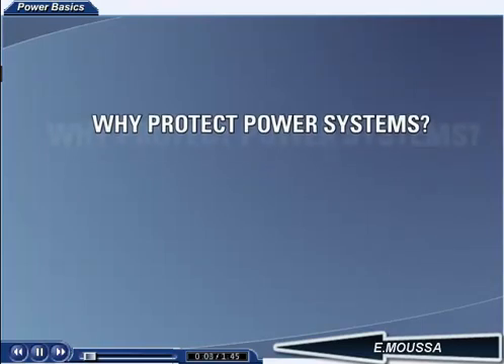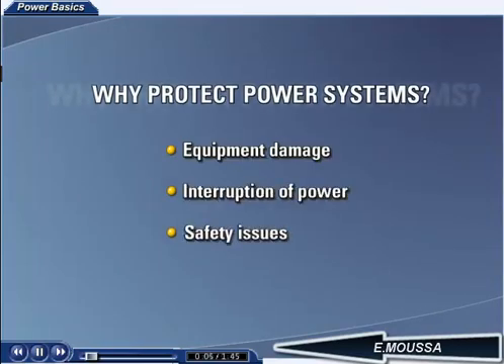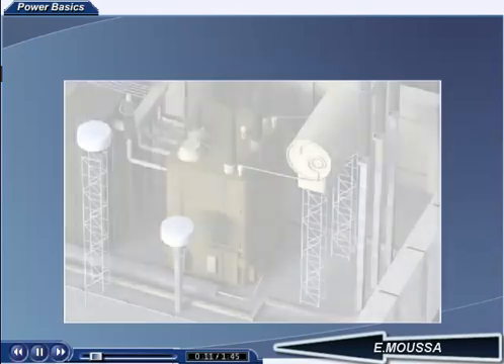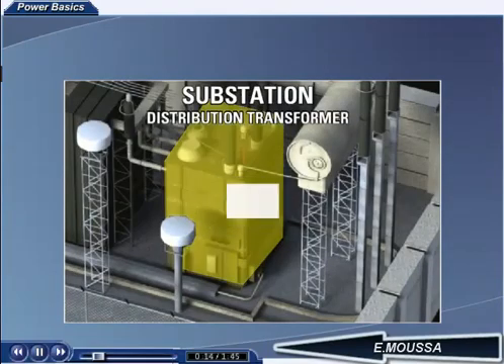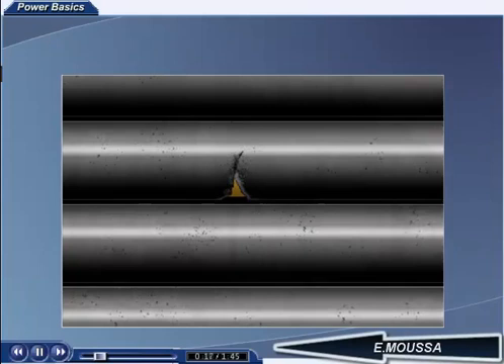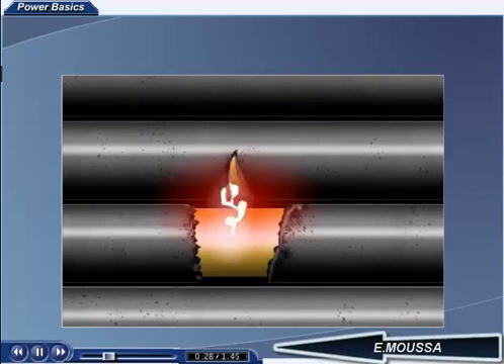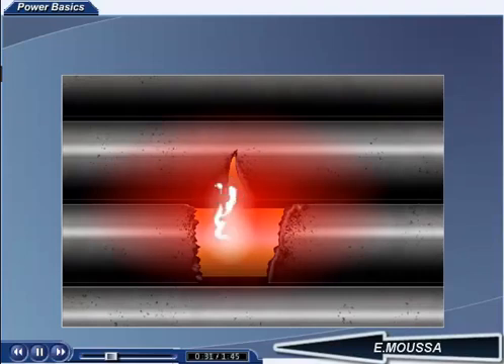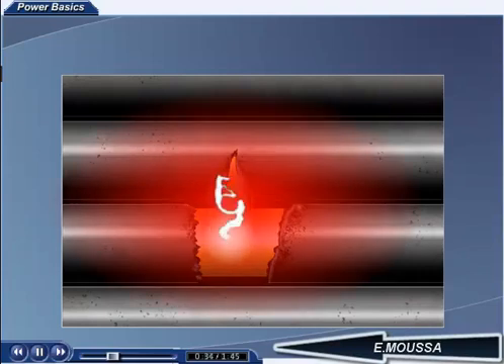The potential costs due to equipment damage, interruption of power, and associated safety issues give a high priority to protection. For example, if a small section of aging insulation in a large distribution transformer fails, high levels of fault current will flow. If the fault isn't isolated quickly, the fault current will cause the conductors to heat. As the temperature of the conductor rises, the damage will spread to the surrounding insulation, causing it to fail, and the fault current will increase even further. As the level of fault current increases, the temperature will rise to a level that will melt the conductors and burn the steel laminations, resulting in catastrophic damage to this inadequately protected transformer.